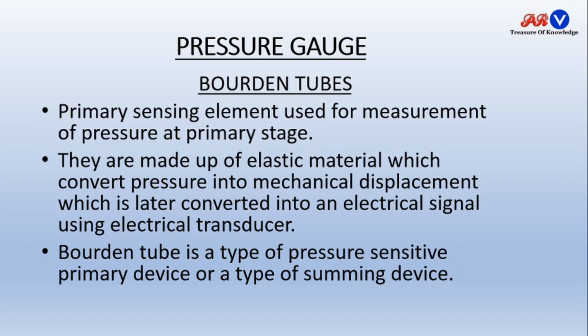They are made up of elastic material which converts pressure into mechanical displacement, which is later converted into an electrical signal using electrical transducer. So these Bourdon tubes are made up of elastic material, and whenever pressure is applied in the Bourdon tubes, there will be a change in the displacement, and this displacement may be amplified by using some methods, and then we can see this displacement on the pointer and scale arrangement, or we can convert this displacement into corresponding electrical signal using electrical transducer.